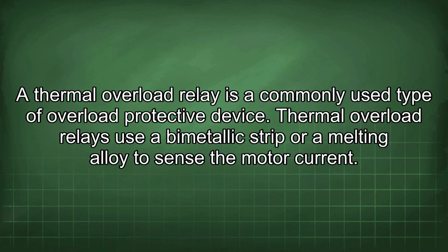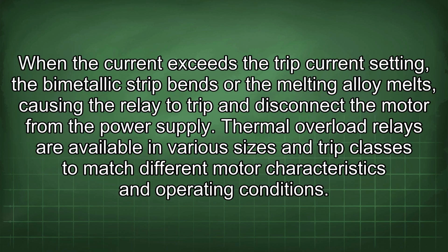A thermal overload relay is a commonly used type of overload protective device. Thermal overload relays use a bimetallic strip or a melting alloy to sense a motor current. When the current exceeds the trip current setting, the bimetallic strip bends or the melting alloy melts, causing the relay to trip and disconnect the motor from the power supply. Thermal overload relays are available in various sizes and trip classes to match different motor characteristics and operating conditions.